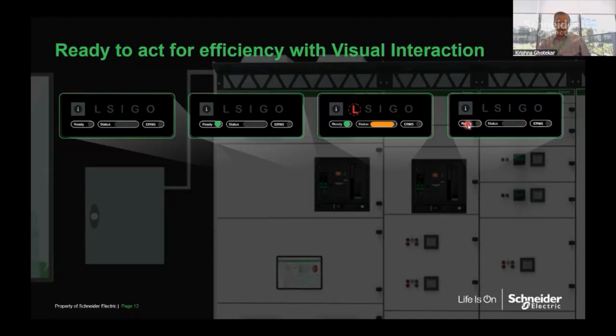So the ready LED will be off because the breaker is in the trip condition. The status will indicate that the breaker has tripped and on what fault it has tripped. So overload, short circuit, instantaneous, ground fault, all those LEDs will be there. In case you had activated the ERMS mode, the ERMS LED will be on.